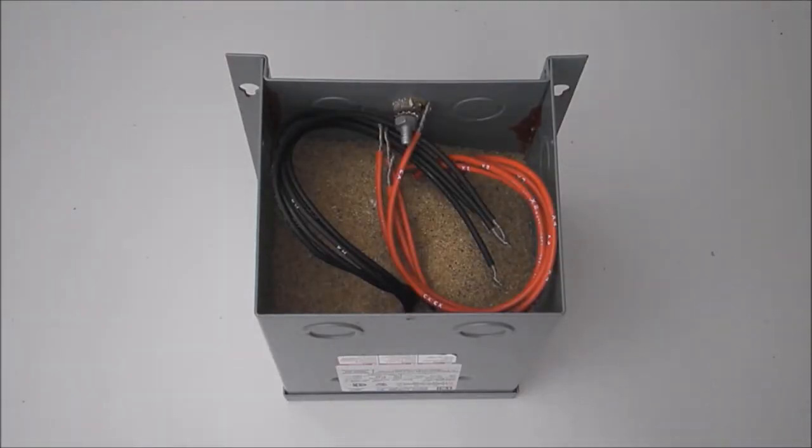One of the most common and popular transformer types in use today are the single phase units with a 480 volt by 240 volt primary and a 240/120 volt secondary. We're going to examine the wiring for an epoxy encapsulated transformer here, but the H connections and X connections will be the same across all transformer sizes and wiring types.